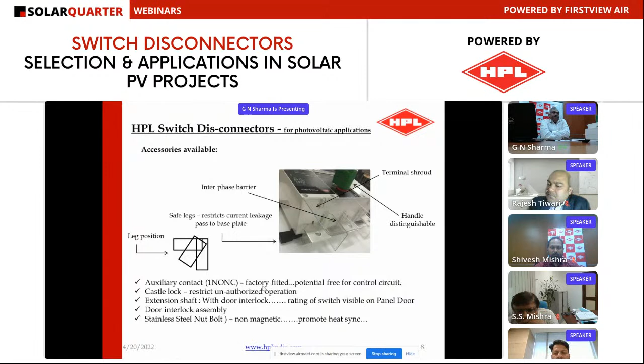We also realized that for termination, most competitors use magnetic steel bolts. With our test facilities, we compared and found that using stainless steel non-magnetic fasteners for termination gives a great reduction in temperature rise of the product, which helps in long service life in the application.